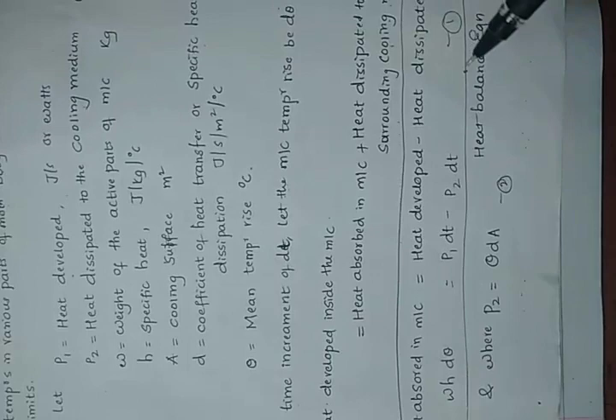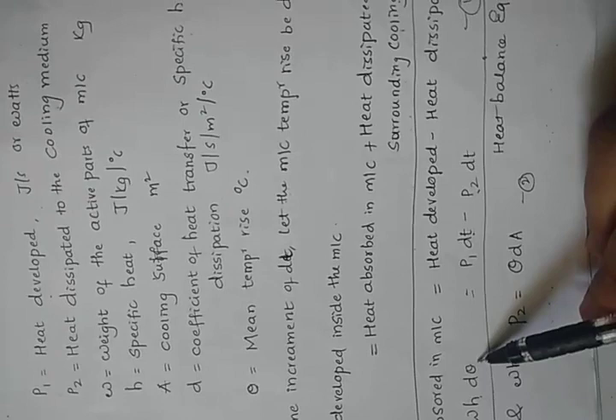W is the weight of the machine, H is the specific heat, P1 is heat developed, P2 is the heat dissipated. dt means time interval dt, and the temperature increment is d theta. So P2 is equal to theta D A. Theta is the mean temperature, D is the coefficient of heat transfer, or you can say specific heat dissipation, and A is the area. So P2, the heat dissipated, depends on these three parameters.